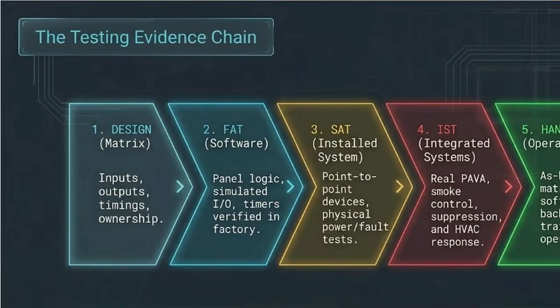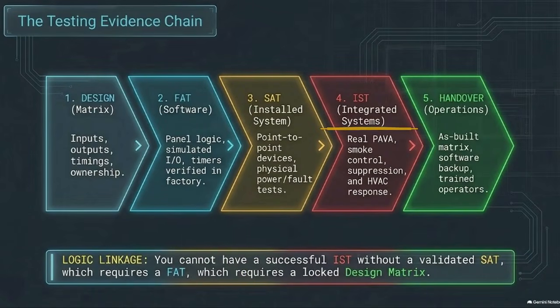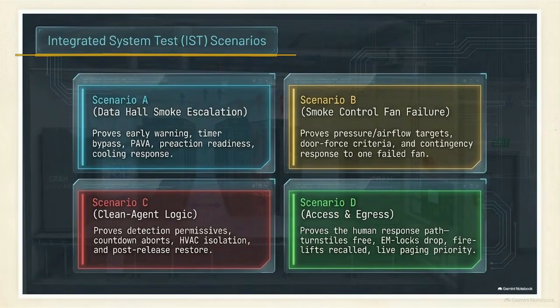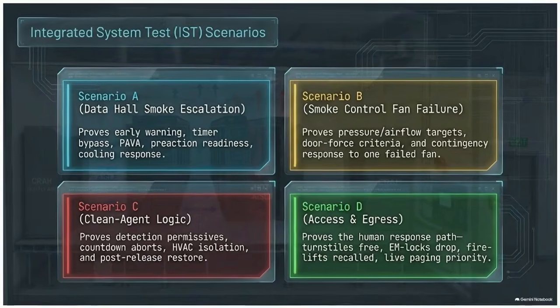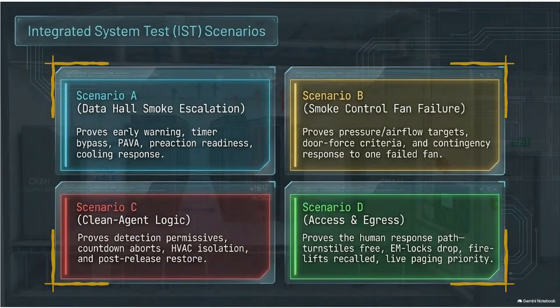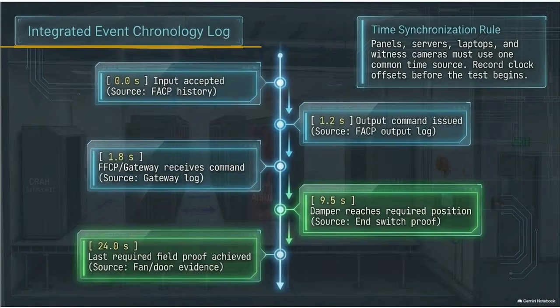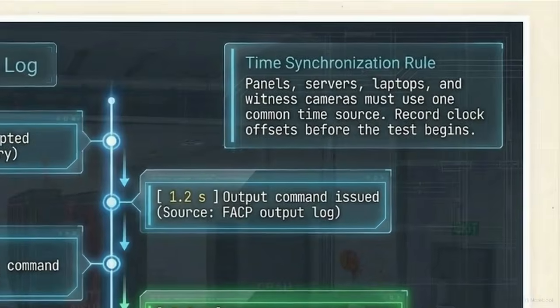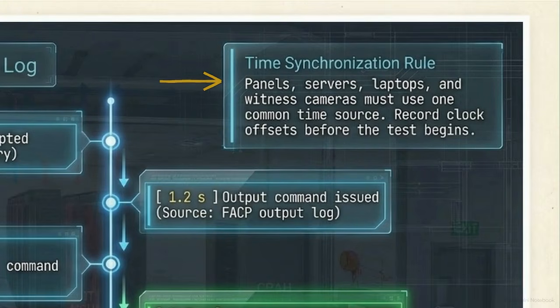This flow diagram maps the testing evidence chain. Software testing of panel logic at the factory is necessary, but it is meaningless without real-world physical integration testing at the facility. The matrix must pass specific integrated system test, or IST, scenarios. These colored blocks outline tests for data hall smoke escalation, clean agent logic aborts, and critically, contingency responses to physical fan failures. This event chronology log establishes the strict rules for those tests. Before an IST begins, every fire panel, server, laptop, and witness camera must be synchronized to one common time source.